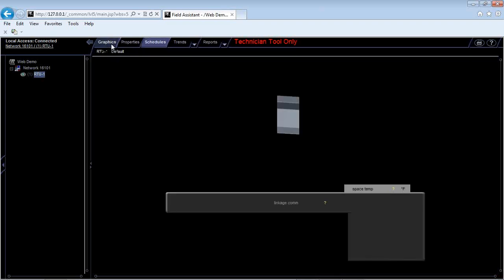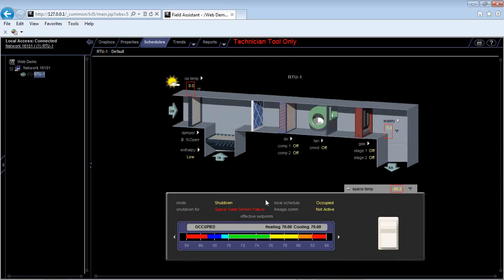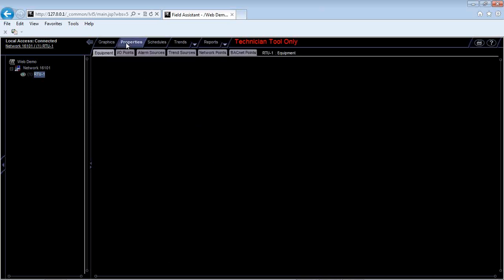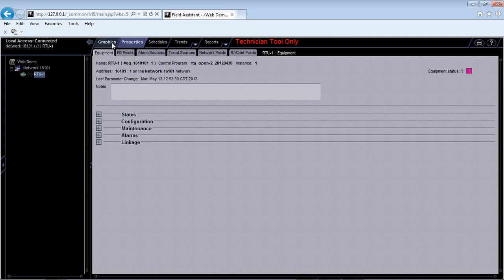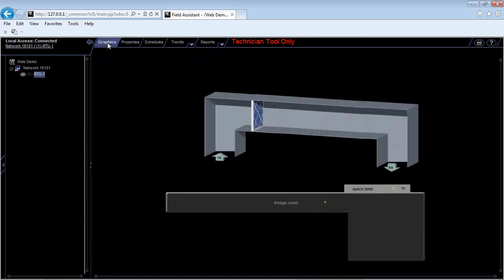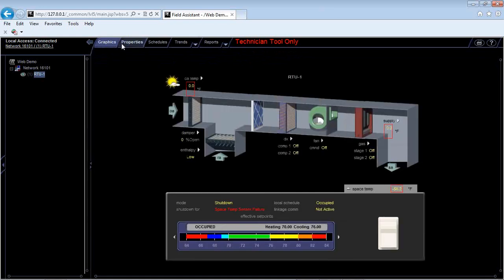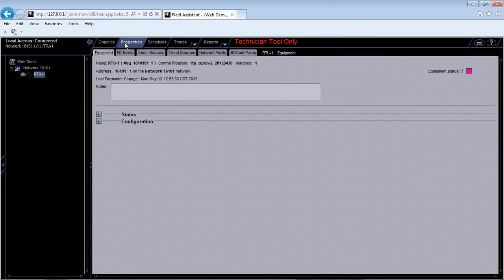Now if I look at my graphics, my unit should say local schedule occupied, okay? Right now I'm reading a space sensor failure because I don't have a space sensor wired in, but I can trick my unit to think that I have a space temperature sensor. So real quick, we're going to look at the last 4 tables here and try to squeak them in.